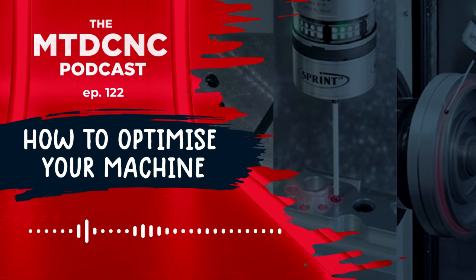So by measuring a sphere, or basing the probe into a small cone on the table and rotating the table, we can check the linear and rotary axes on the machine prior to carrying out any machining. That can be done in a matter of seconds, as a very quick go, no-go check. And then, obviously, if it fails, we would recommend that you move on to the ball bar and axis set and then thoroughly check the machine.